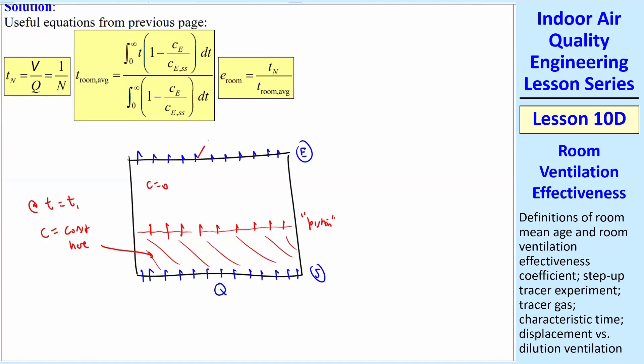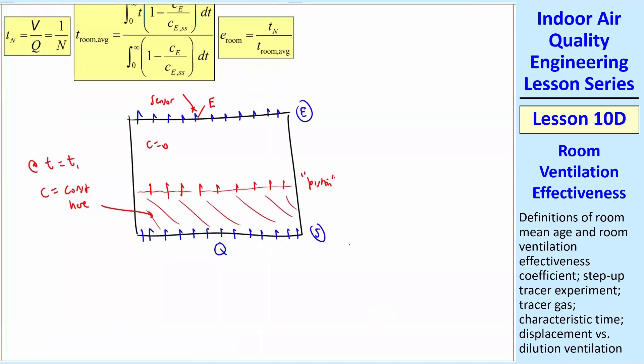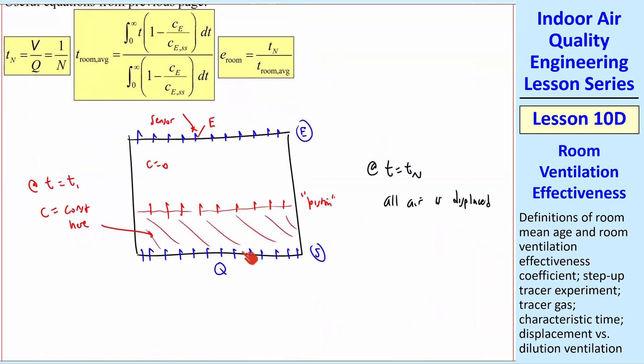And you can think of this interface between the contaminated air and the clean air is like a piston pushing the stale air out. Everything's uniform right to left and front to back in this room. There's nothing special about any one place. So you can pick any of these and call that E and put your sensor there and measure CE as a function of time. By the way, at T equal TN, we know that all the air is displaced. How do I know that? Because TN was 1 over N, and N is the number of room air changes, or it's a volume over Q. So in other words, TN is the time it takes to displace one room air volume if I deal with displacement ventilation in a case. Well, that's what we're talking about.